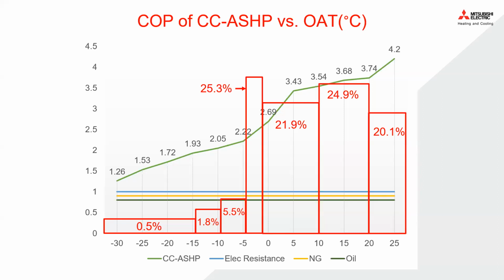So this chart here is an efficiency curve for a 3-ton Zuba system being compared to conventional systems. We have electric resistance at 1, natural gas at 98, and oil, let's say 85, but they're constant, right? It doesn't matter what the outdoor temperature is, they're going to stay at that same level. Now, when you look at the heat pump, you've got this curve that starts very high when the temperatures are warm and gets down low, but you still stay above a COP of 1. So as far as energy efficiency is concerned, it's still doing better than the traditional systems.